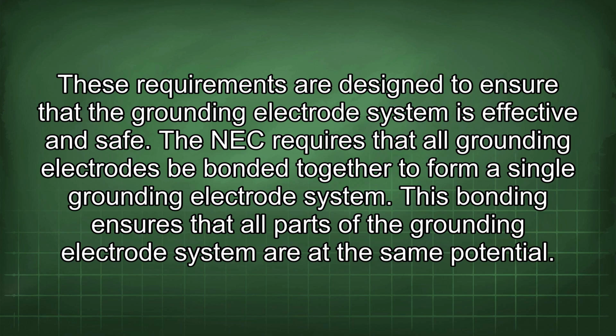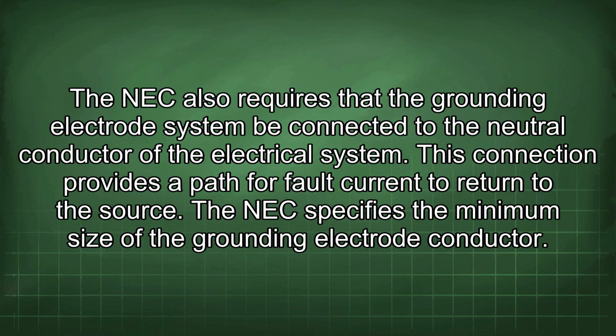The NEC requires that all grounding electrodes be bonded together to form a single grounding electrode system. This bonding ensures that all parts of the grounding electrode system are at the same potential. The NEC also requires that the grounding electrode system be connected to the neutral conductor of the electrical system. This connection provides a path for fault current to return to the source.